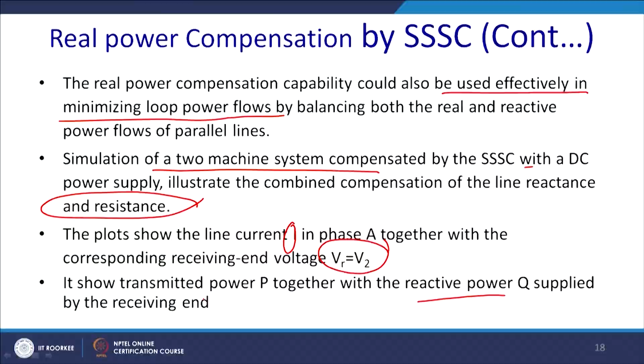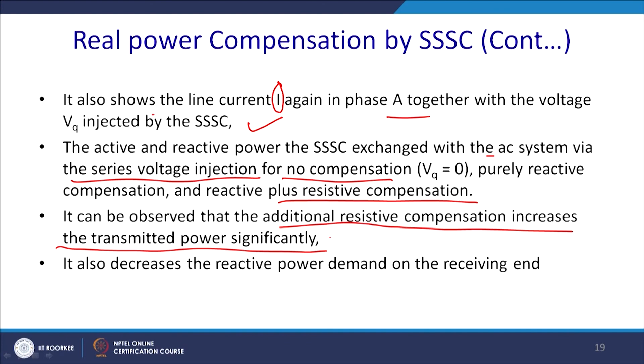The active and the reactive power in the SSSC are exchanged with the AC system via series voltage injection; for no compensation, VQ is 0. Purely reactive compensation and reactive plus resistive compensation can also be done here. It can be observed in the previous curve that the additional resistive compensation increases the transmitted power significantly. It also decreases the reactive power demand at the receiving end. So, these are a few characteristics of real power flow through the SSSC.